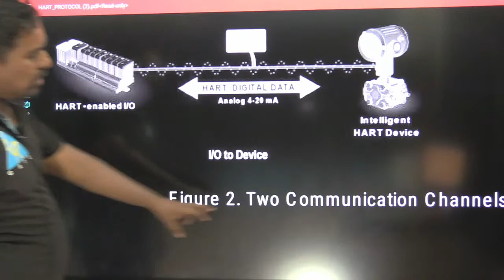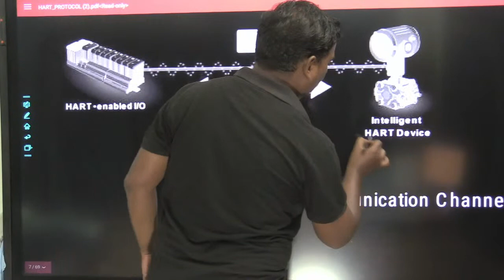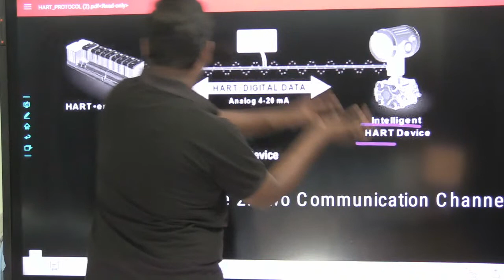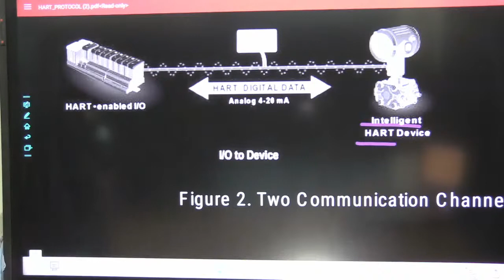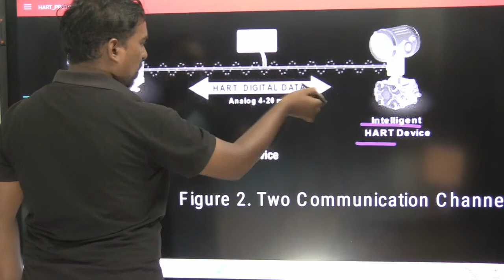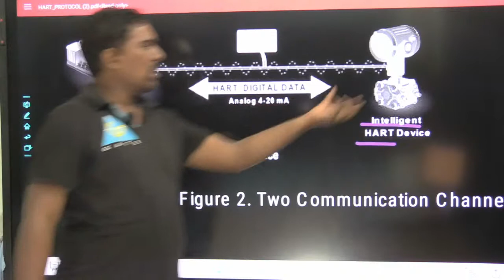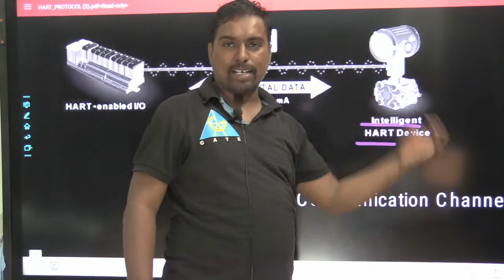See here. This is a HART enabled IO device, this is an intelligent HART device, this is our sensor. I use the words intelligent HART device, that means it should have some HART settings. It should be in a position to be configured by this particular controller. That's what is called an intelligent HART device. Now, this is the data which is coming from this particular device, and I am using the 4 to 20 milliamperes, and HART digital data is coming. HART digital data means what? This device information: which particular device it is, what is its status, what are the diagnostics, what are the configuration settings for that, all that information.